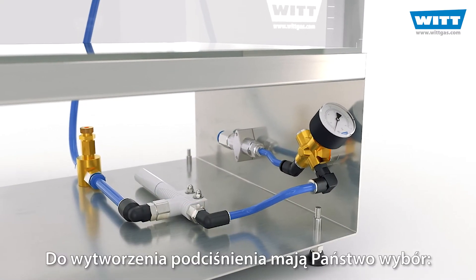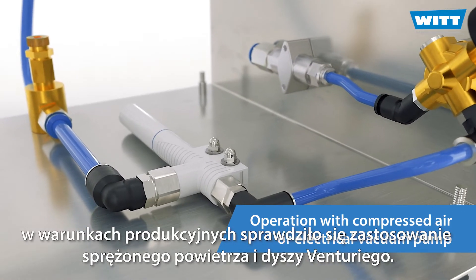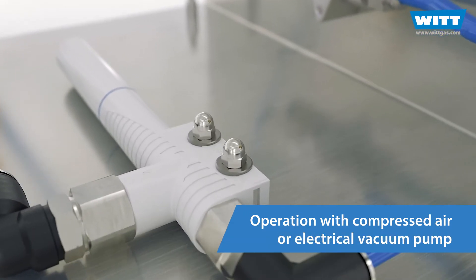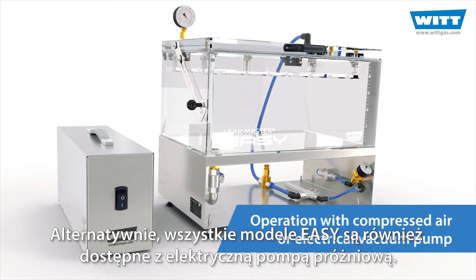To generate the vacuum, you have a choice. In production environments, the use of compressed air and a Venturi nozzle has proven successful. Alternatively, all EASY models are also available with an electric vacuum pump.